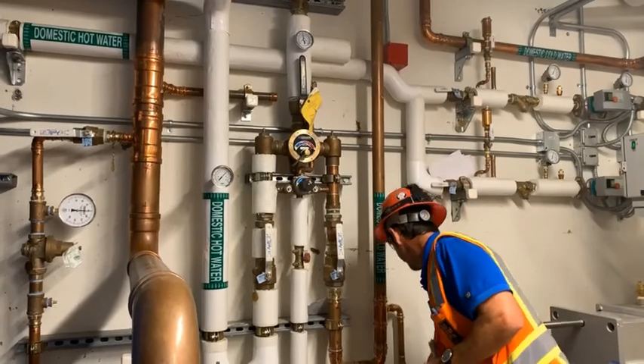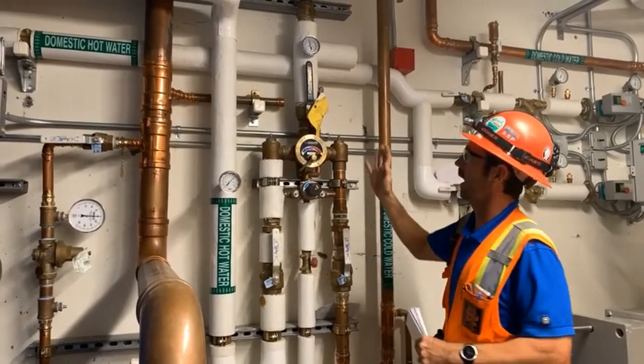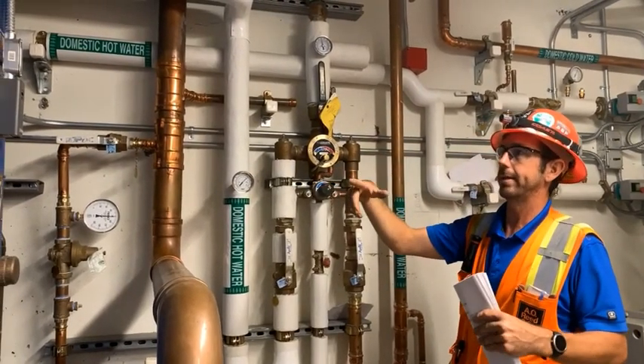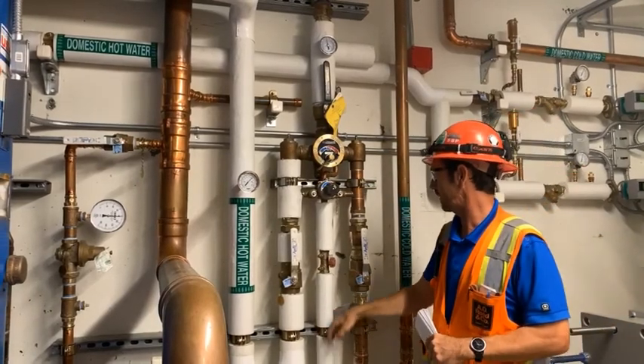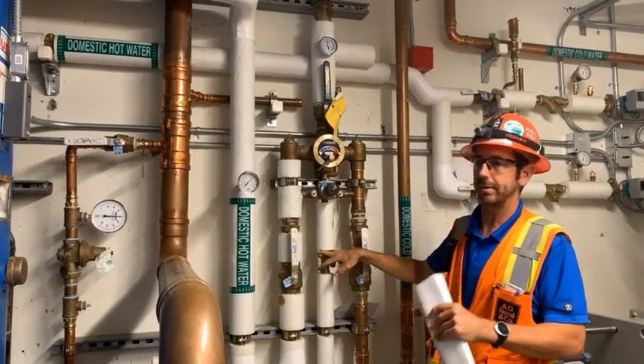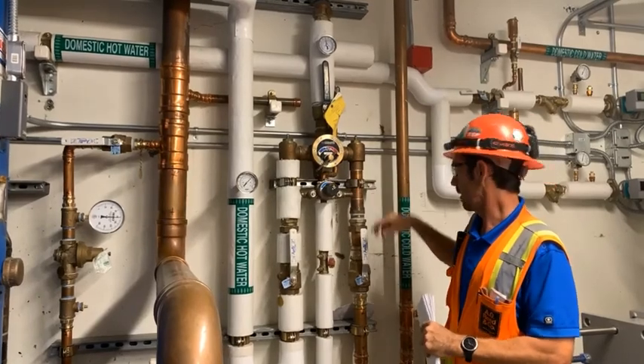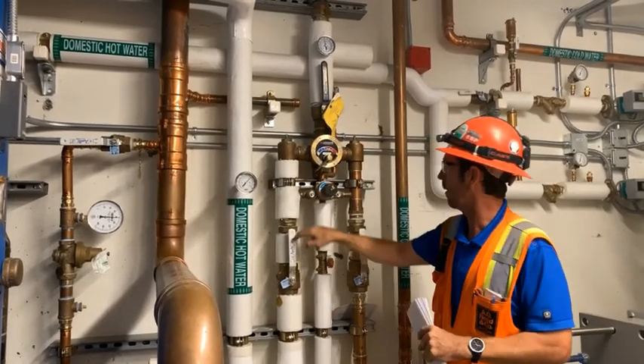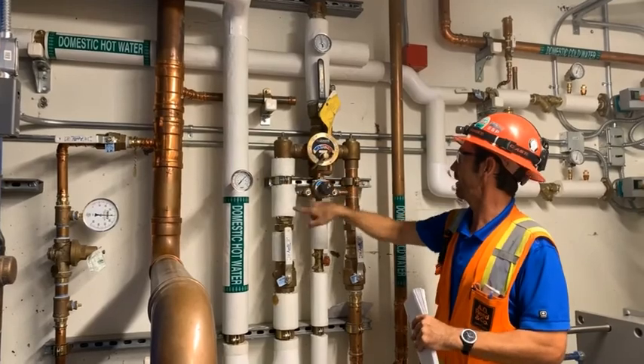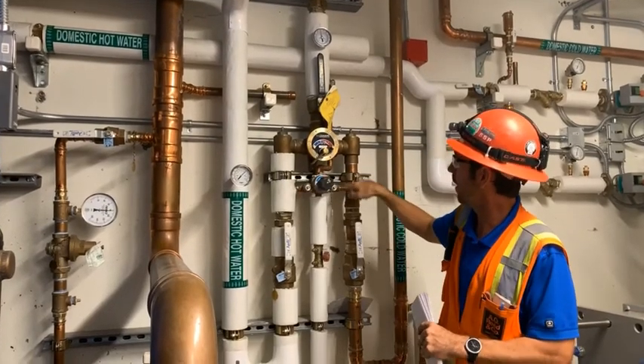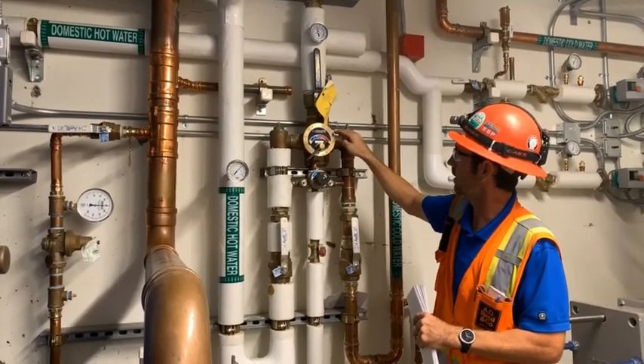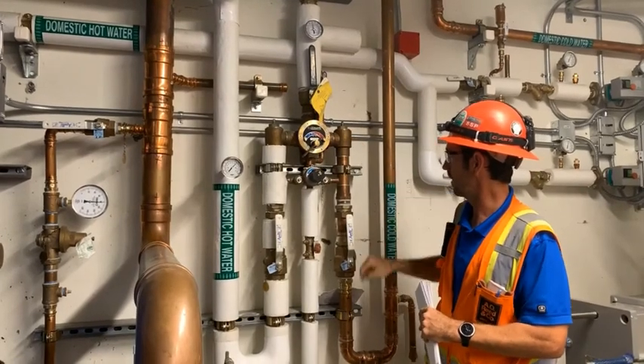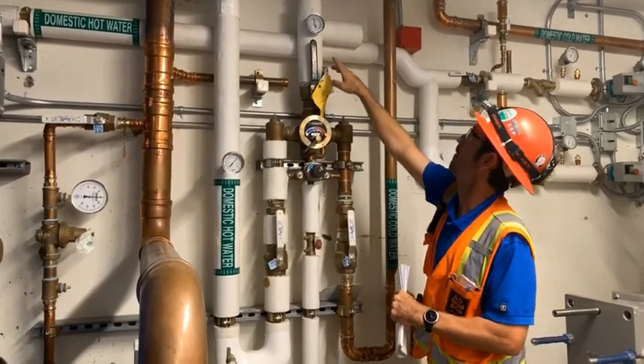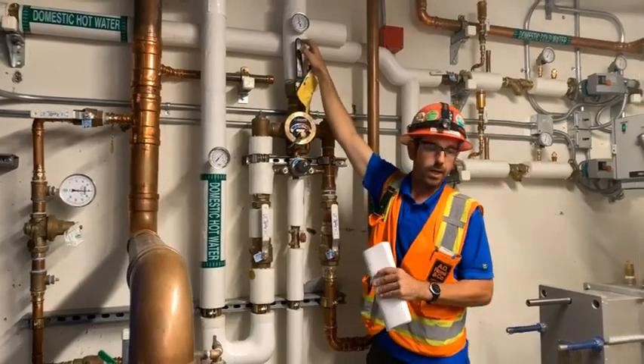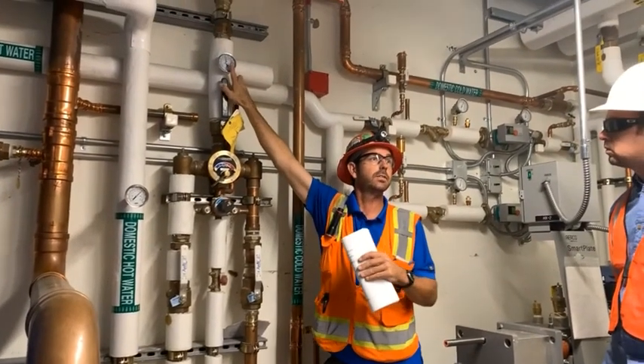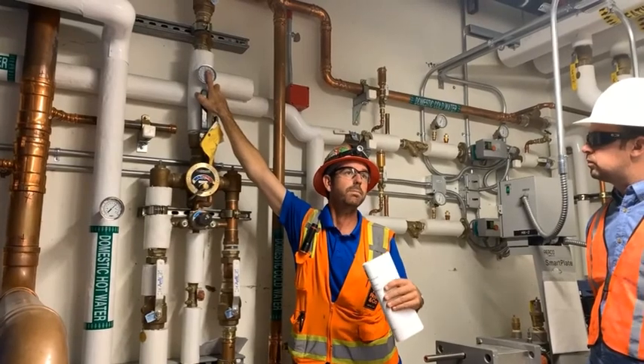So this line right here is putting water into the 140 degree loop, and we'll get into that in a sec. The other line is just mixing the return loop that's like roughly 110 or so coming back into the mixing valve. So it'll always be pushing a little bit of hot water on this side through the valve, through the lower one. The pump only runs through this lower valve, okay, not the upper valve, okay? So it'll always be pushing water through the valve and we'll be able to see that temperature. It is very crucial that this temperature does not drop below 120.